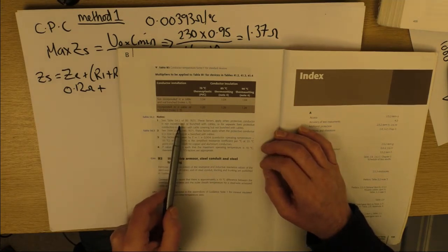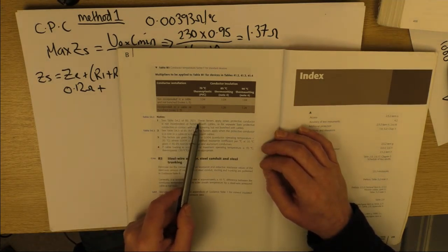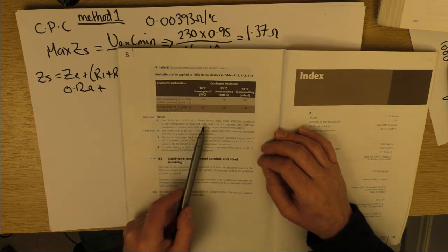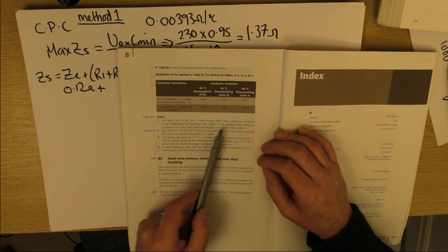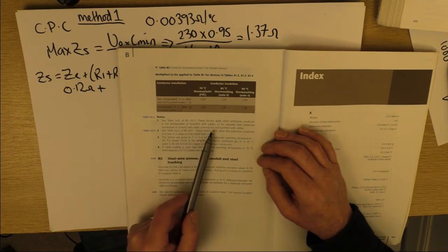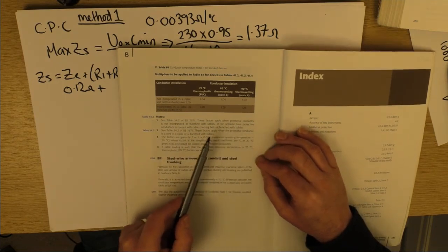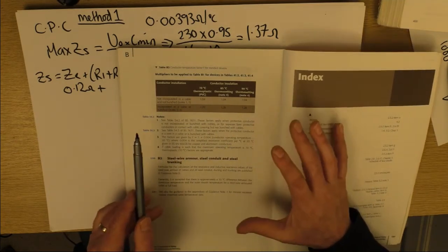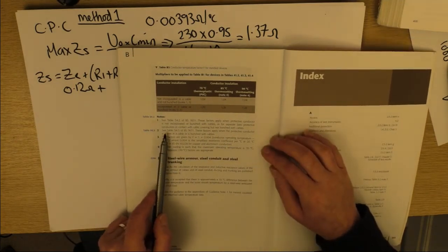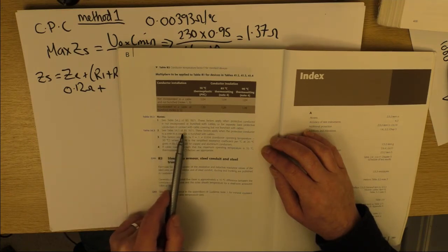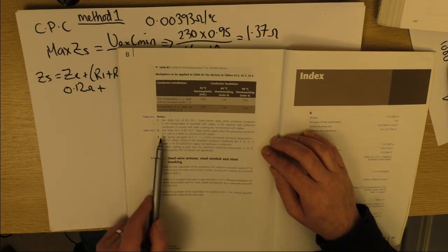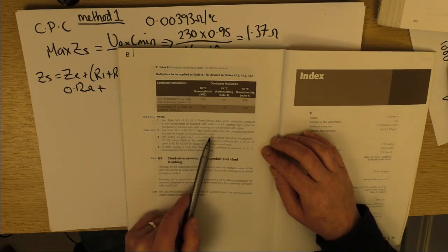Note 1: see table 54.2 of BS 7671. These factors apply when the protective conductor is not incorporated or bunched with cables, or for separate bare protective conductors in contact with cable covering but not bunched with cables. A picture would be nice, I think. Certainly would make it a lot easier. And then note 2 for this one: see table 54.3 of BS 7671. These factors apply when a protective conductor is a core in a cable or is bunched with cables.